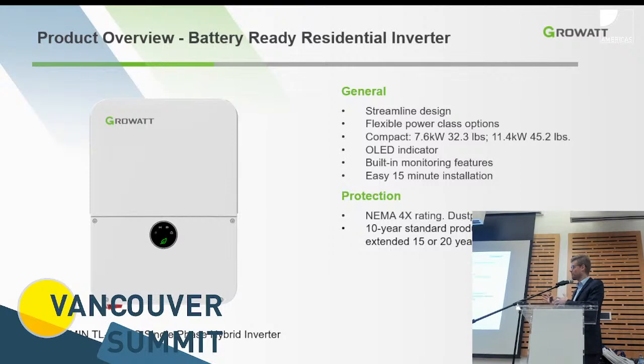So if it's just an inverter that you use for a solar system only, no battery backup, the system will ask you, do you have a battery, once you go through the commissioning process, and you say no, and then it's pretty much done. Versus if you have a battery system and backup, then there are more steps in that configuration process that you go through to commission the system.